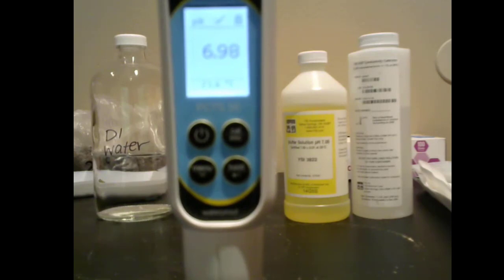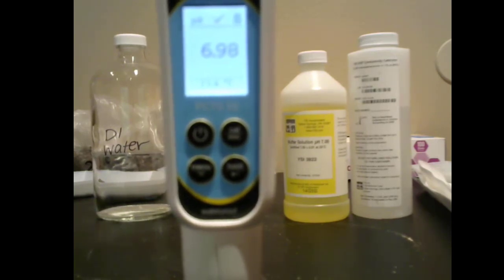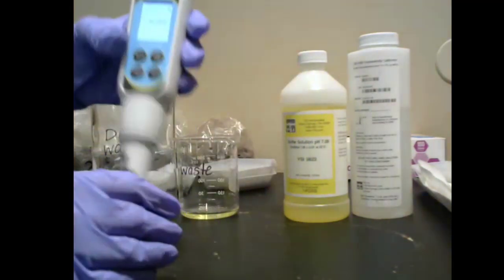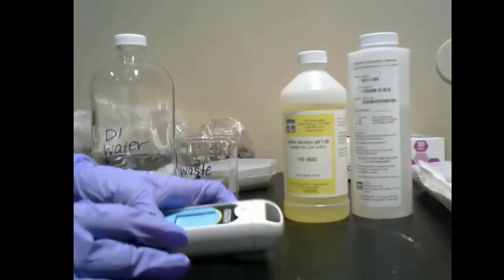6.98. Our pH standard or buffer solution was pH 7. So that's quite a good spot check. And you can input that data into table 4 of our lab and go ahead and complete the table for pH. Now let's go ahead and move on to our conductivity spot check.